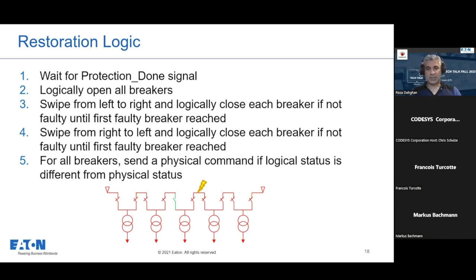After step 4, we know which breakers should be open or closed. So the last step is for all breakers to match the physical status of the breaker with the logical status. We'll send a physical command if the logical status is different from the physical status. Next page.